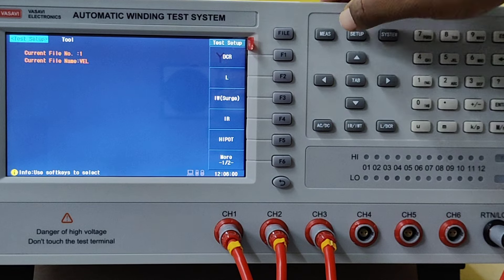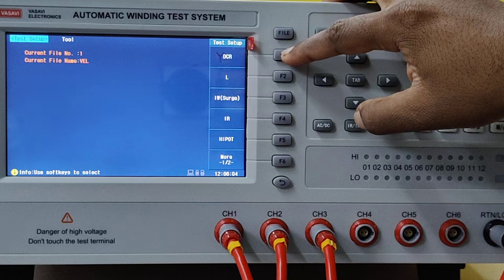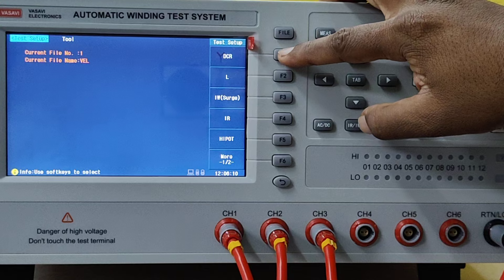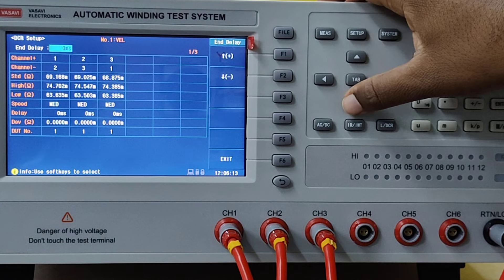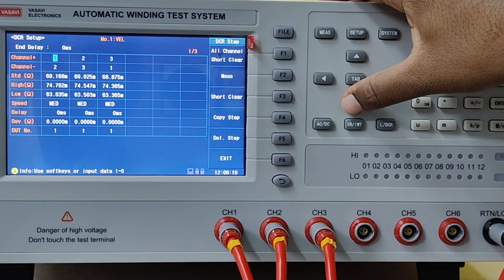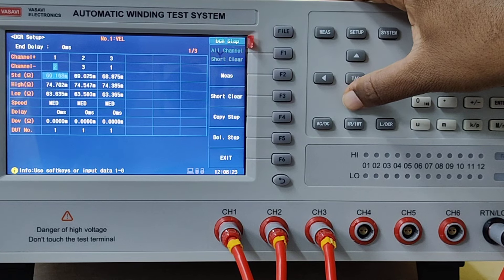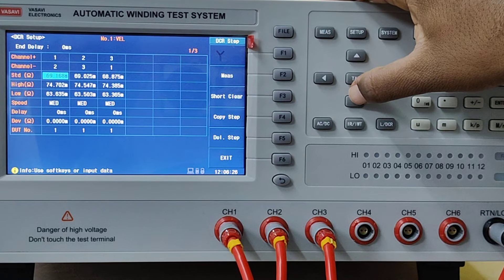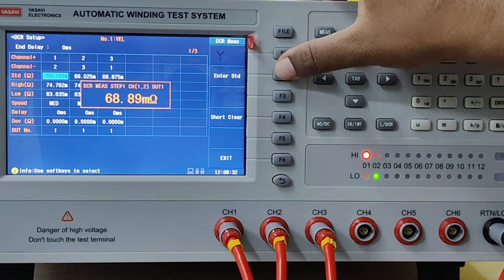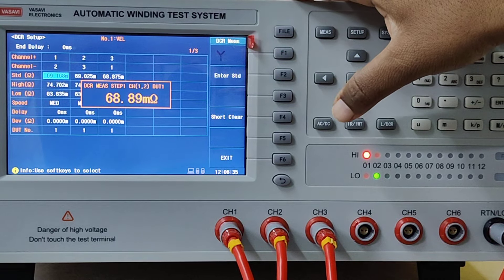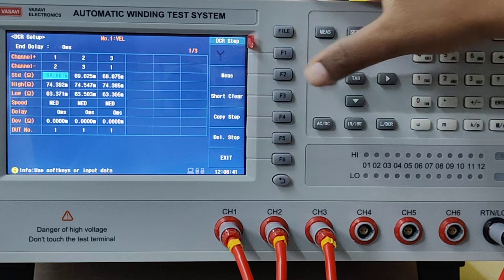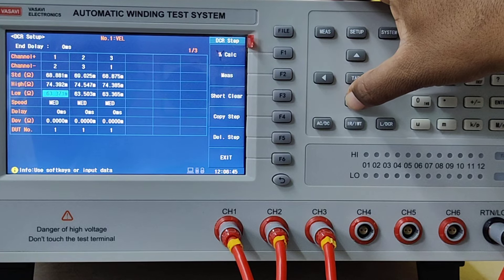Now I will show you how to program for a DC resistance measurement. Press the relevant function button F1 for DC resistance. Select the channel — 1 represents the first channel, 2 represents the second channel. Go for the standard value. If you know the value, punch the value, or you can simply press Measure Value, where it shows the exact measuring value for the standard coil. If you are satisfied, select Enter Standard. Then give the upper limit and lower limit.